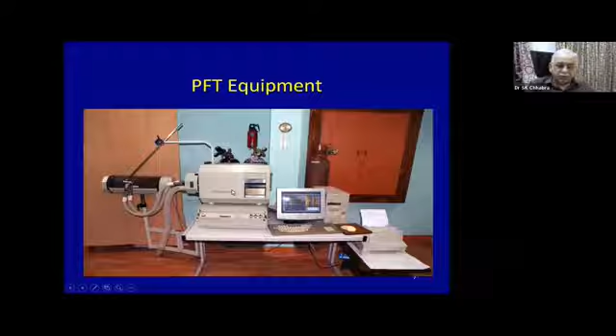Then the other things that are required in doing spirometry are mouthpieces. These mouthpieces may be disposable or reusable, which can be autoclaved. Now this one on the left is a silicone rubber mouthpiece. So this has got this thin plate. This comes between the lips and the gums, and this gives a tight seal. So the teeth will come on these processes here.